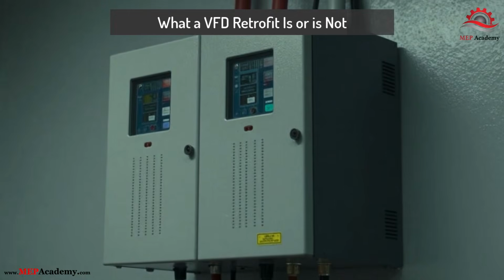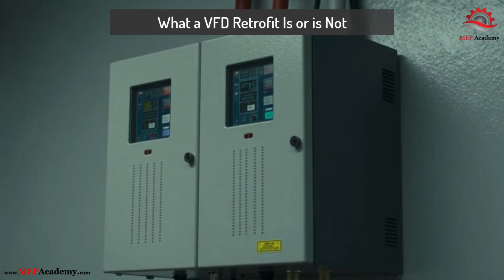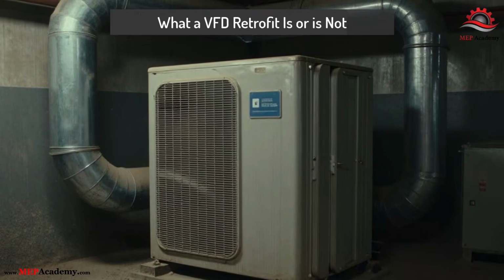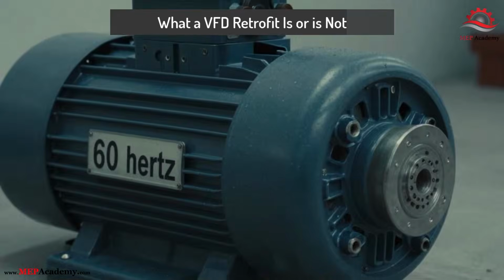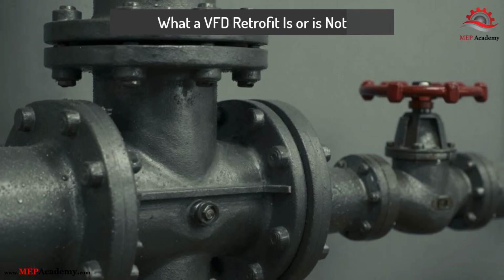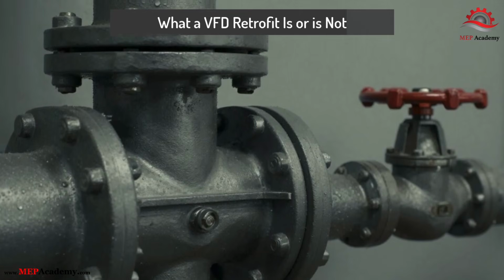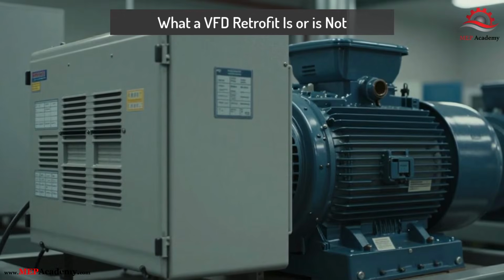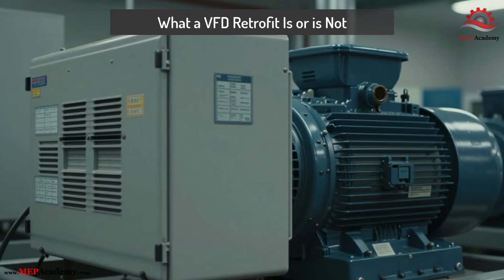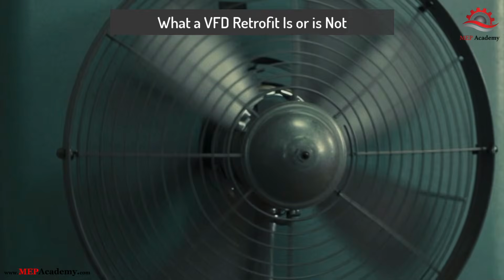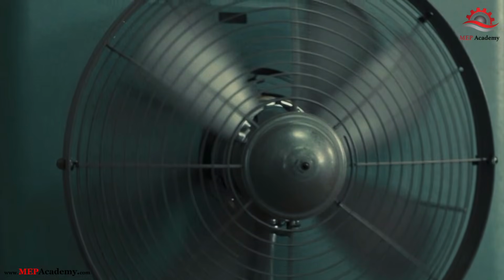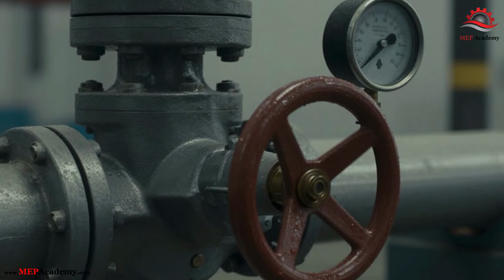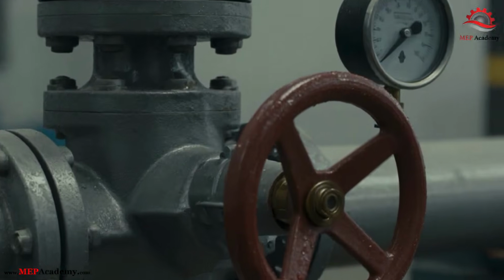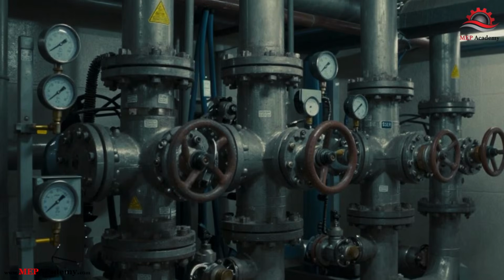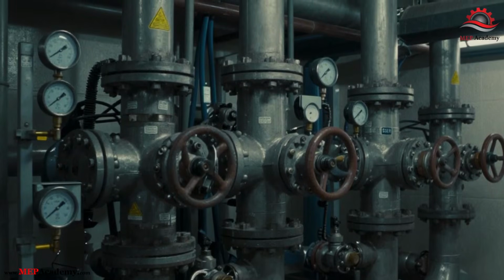Section 1. What a VFD retrofit is and is not. Most older HVAC systems were designed as constant volume systems. The motor runs at 60 Hz. Air or water flow is controlled mechanically with dampers or valves. A VFD retrofit replaces or bypasses the starter and allows us to vary motor speed based on demand. The energy savings come from reducing speed, not just cycling on and off. At partial load, even small speed reductions can yield large energy savings. But, and this is critical, only if the system can safely operate at those lower speeds.